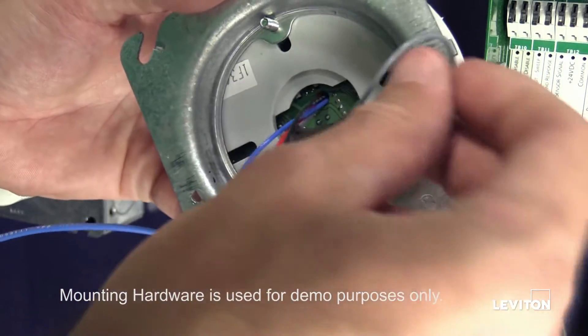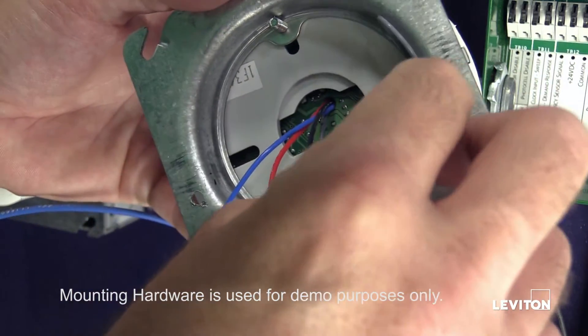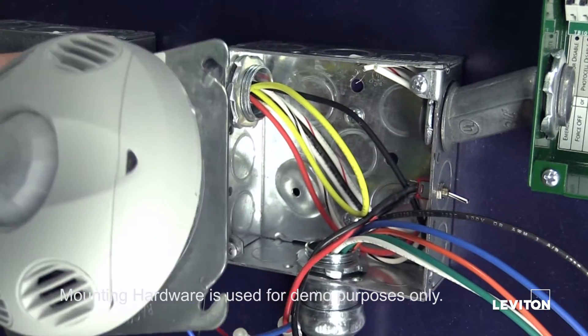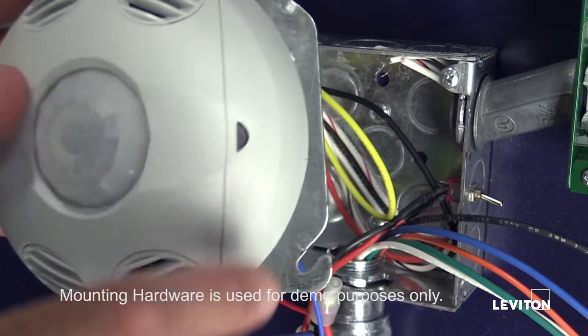The grey wire is for occupancy and hold off photocell. We will be using the blue wire instead. You can use 18 gauge wire or CAT6 cable to extend the wire runs.